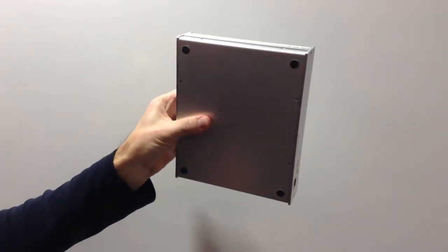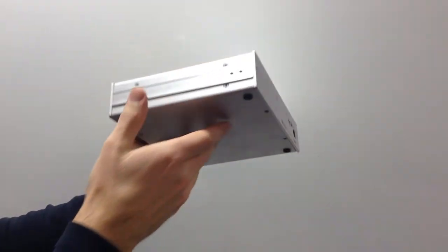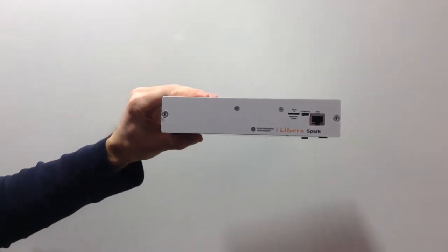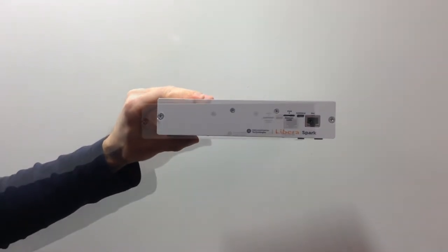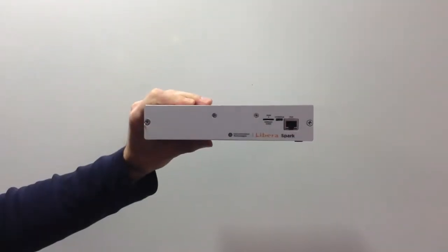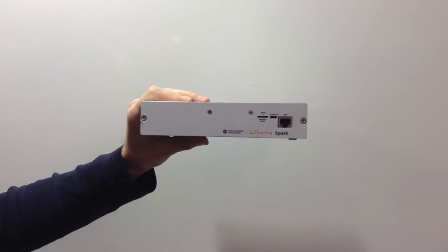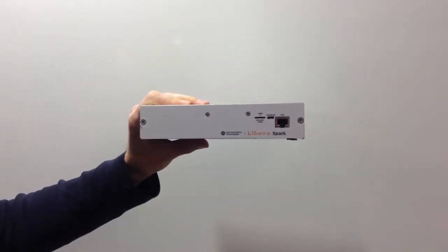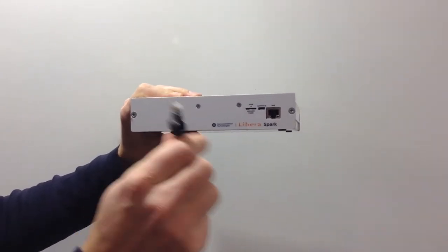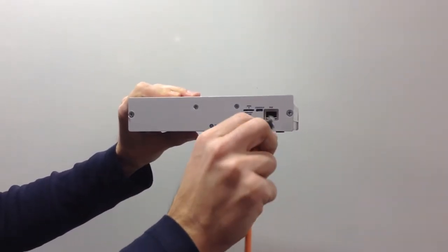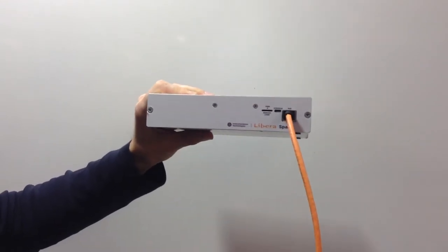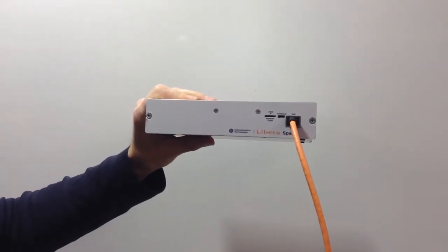The total power consumption is about 10W, so it can be conveniently supplied by power over the Ethernet network switch. It just requires an Ethernet cable to power on. 30 seconds later the first measurement can be read out.